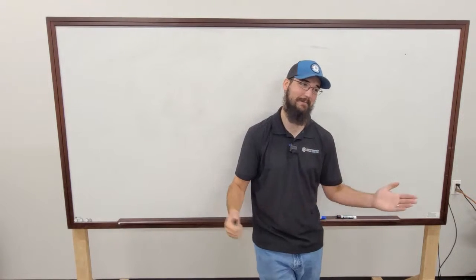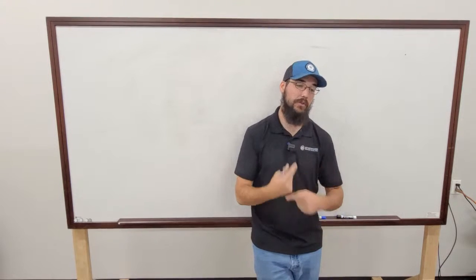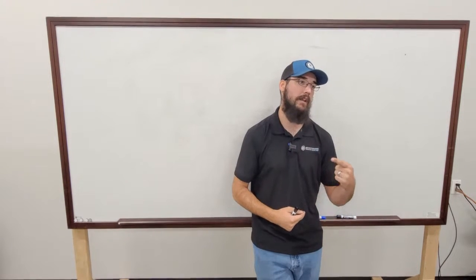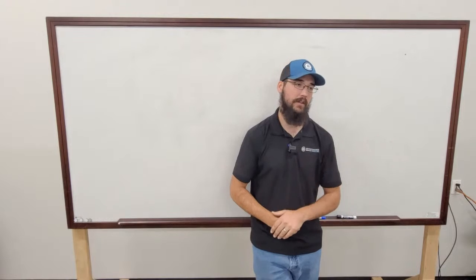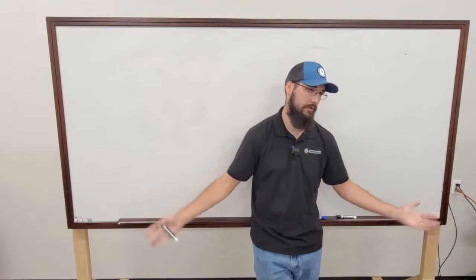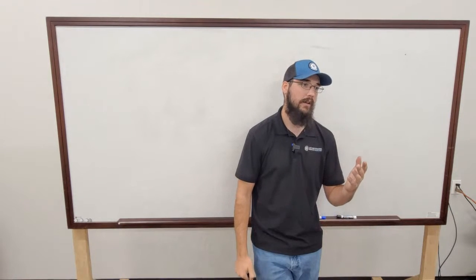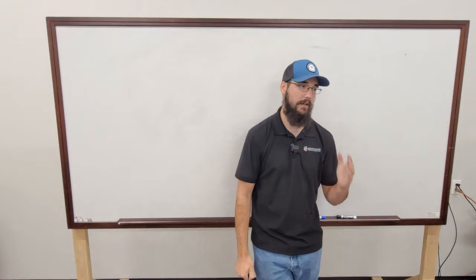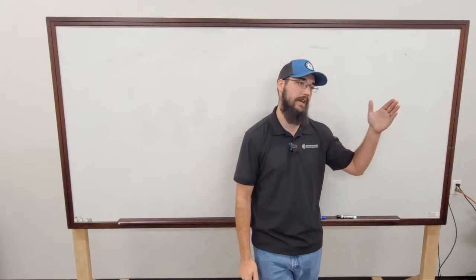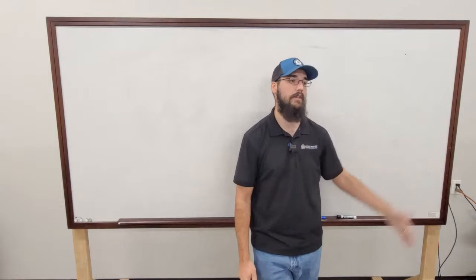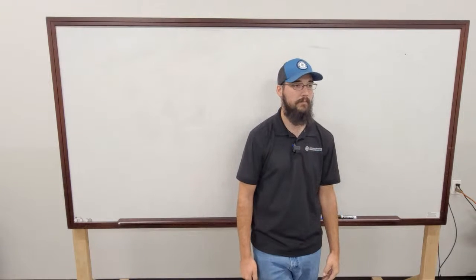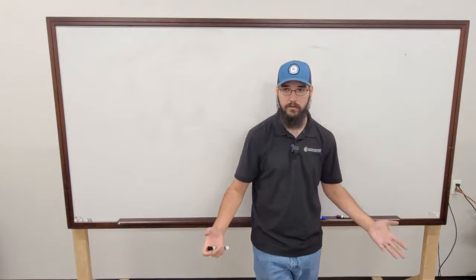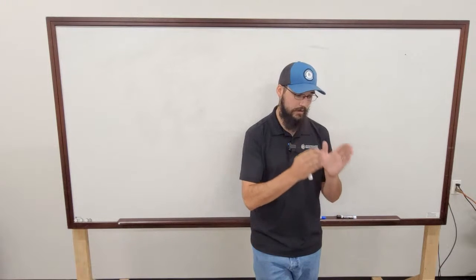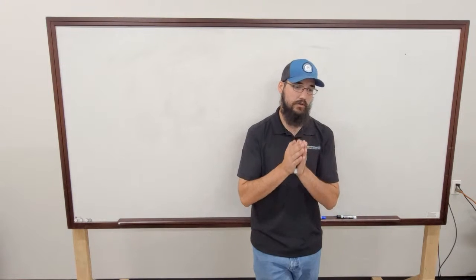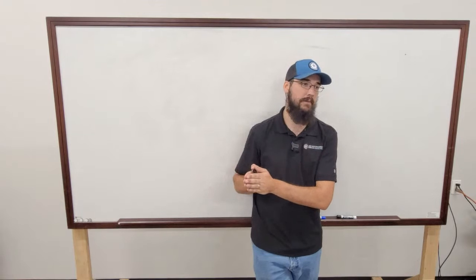I got to give you a hard time. Anyway, I will do it that way because at that point, the machine doesn't care that it sees 100-something degrees entering. Right, that'll get you up and running so you can go get the part. Yes, it is satisfied that the leaving is making set point. So just bear that in mind. It's the leaving water that is controlling everything that happens in that machine.